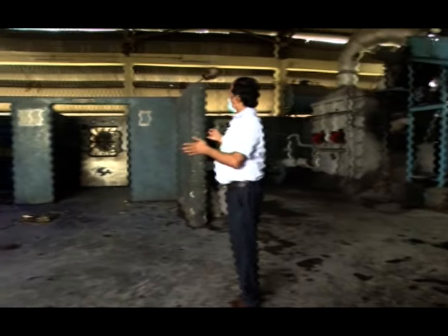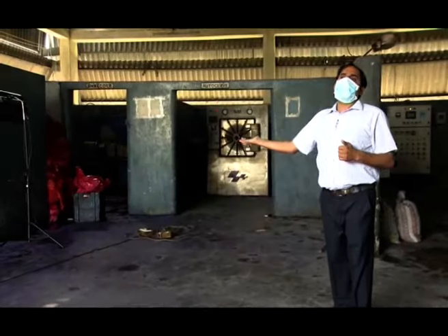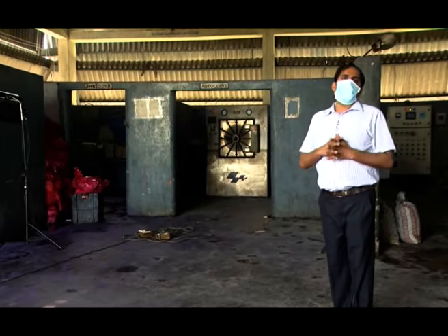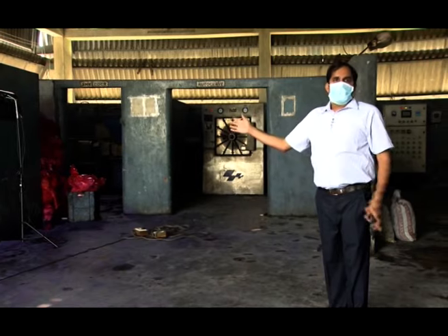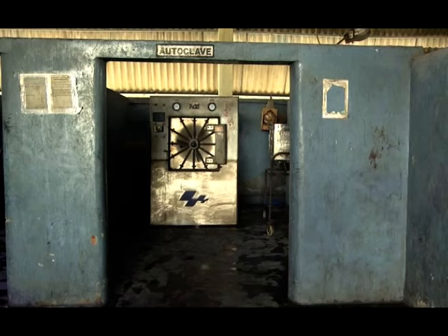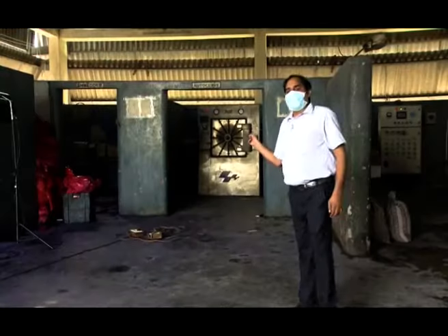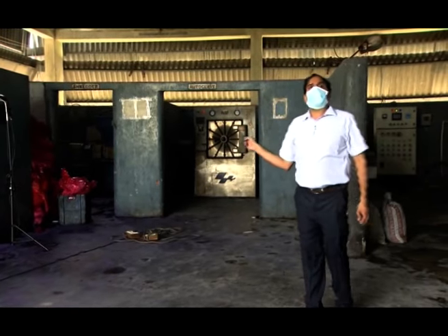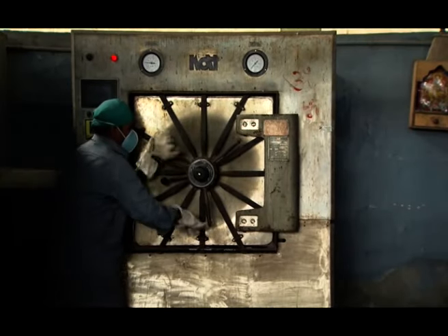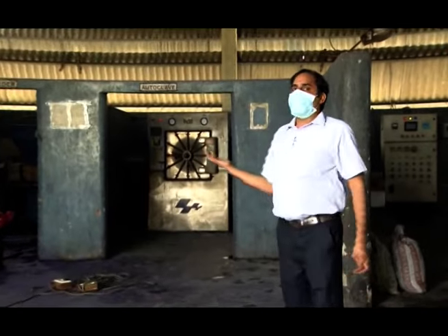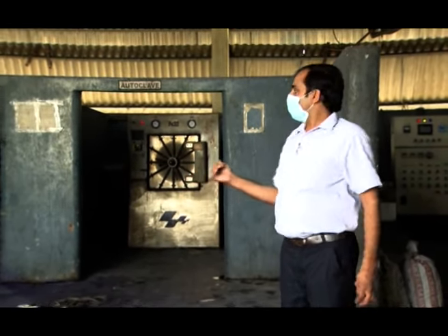We have a disinfection unit. Red colored bags and puncture-proof blue and white bags are kept here, and from time to time this is autoclaved. We maintain a temperature of 121 degrees and pressure of 15 psi. There is a certain time-bound cycle here, and after autoclaving the waste is shredded.